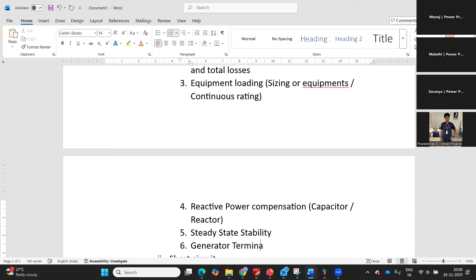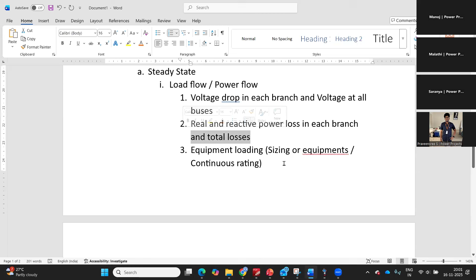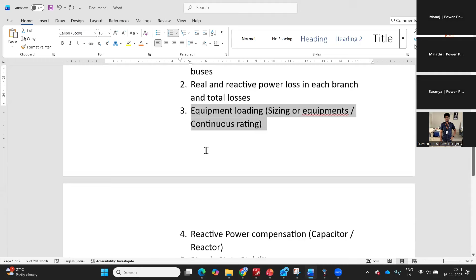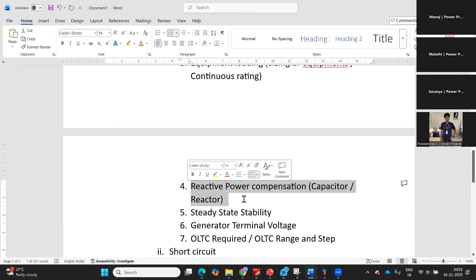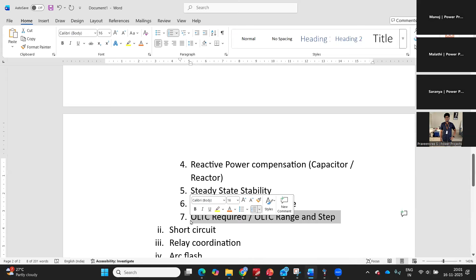So why do we need to perform load flow? To find out the voltage drop in each branch, to find out the voltage at all buses, to find out real and reactive power loss in each branch and the total losses, to find out the equipment loading and check the size of equipments, continuous rating of all equipments, to find out what's the reactive power compensation or capacitor bank or shunt reactor needed, to check and ensure the system is steady state stable or not, to identify the generator terminal voltage set point, and also to check whether the transformer OLTC is required or not. If needed, what's the range and what's the step.